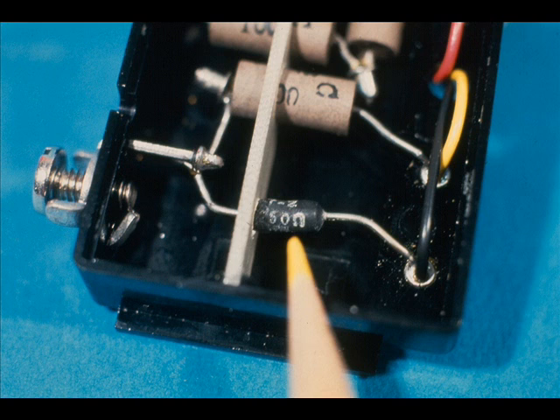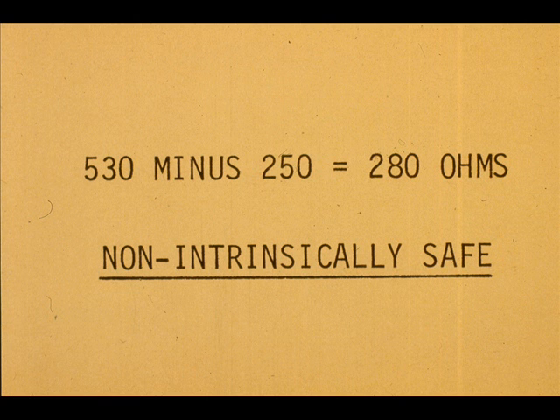A Veritrac receiver contains 250 ohms of signal input resistance. This must be subtracted from the total of 530 ohms. 530 minus 250 leaves 280 ohms allowable signal wire resistance. This is for a non-intrinsically safe receiver.